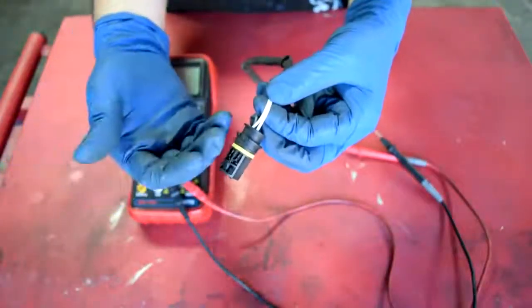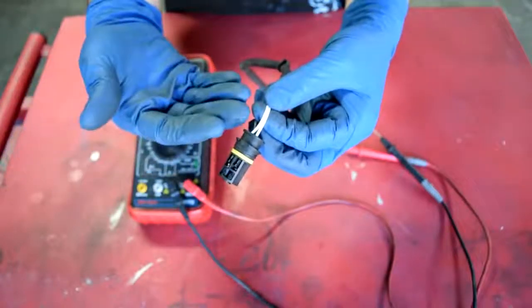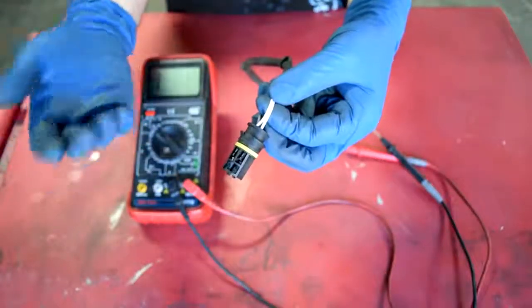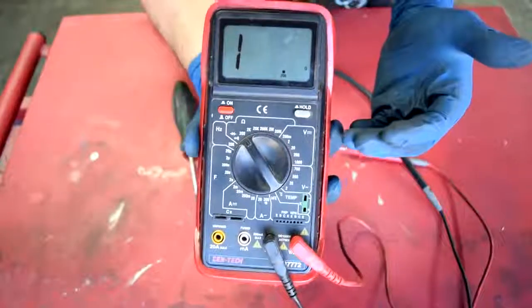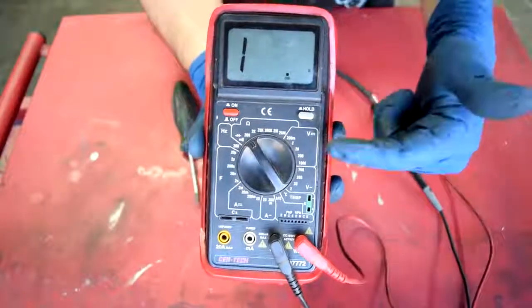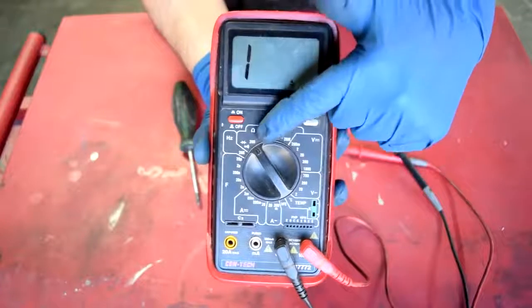The 2 wires for the heating circuit are usually the same color, usually either white, black, or sometimes gray. We're going to do a resistance check on this sensor. So we grab our multimeter, put it on the ohm setting, and we're going to choose 200.